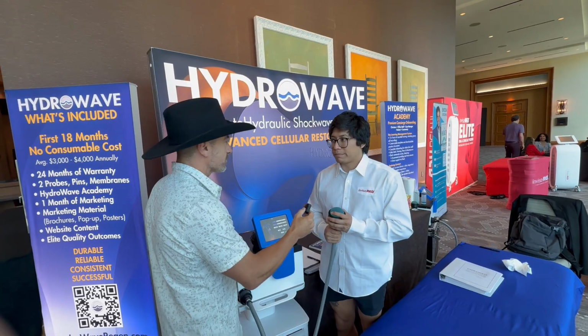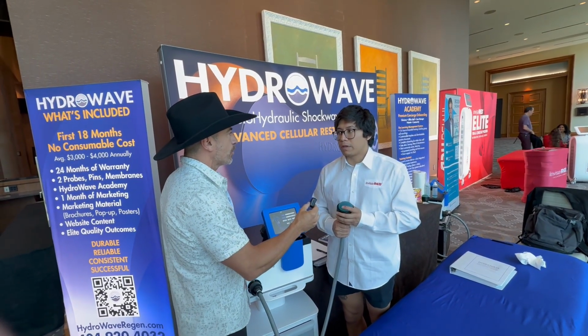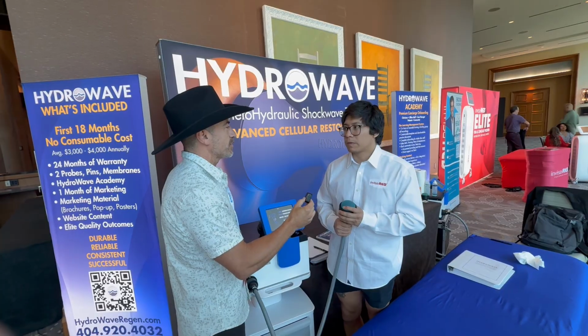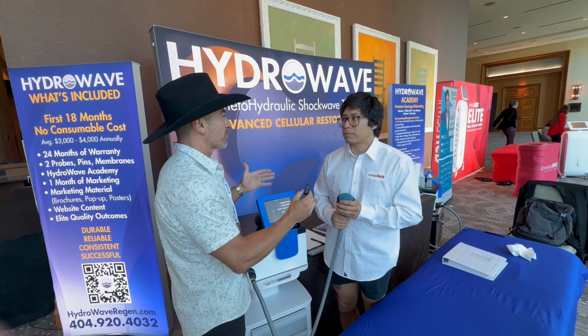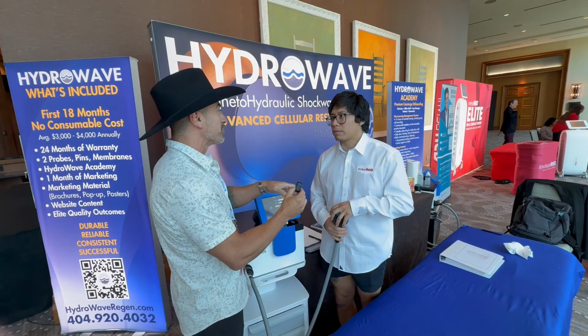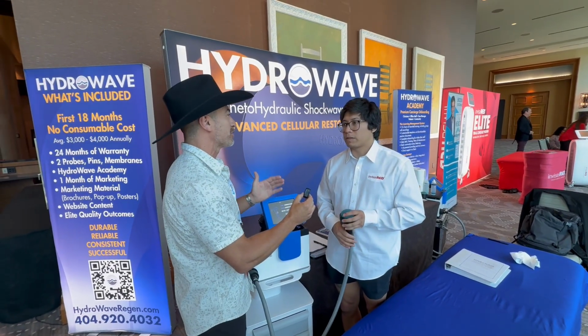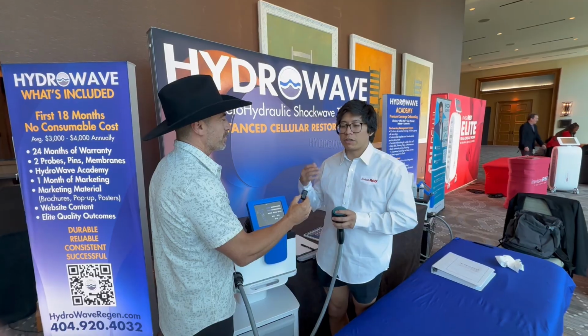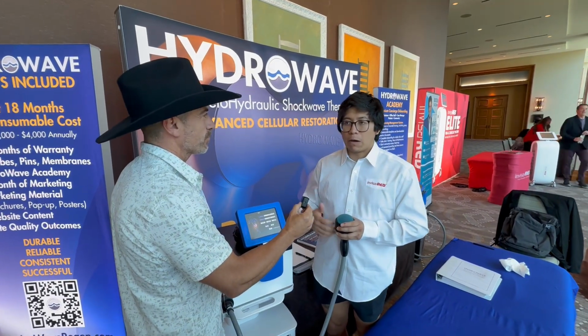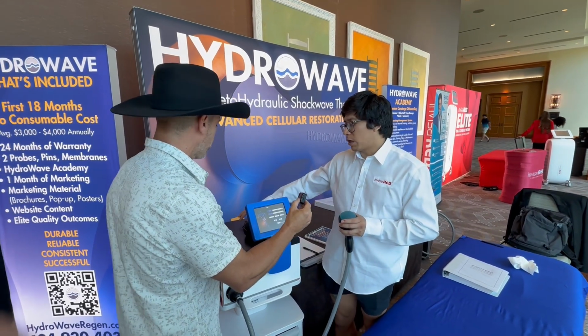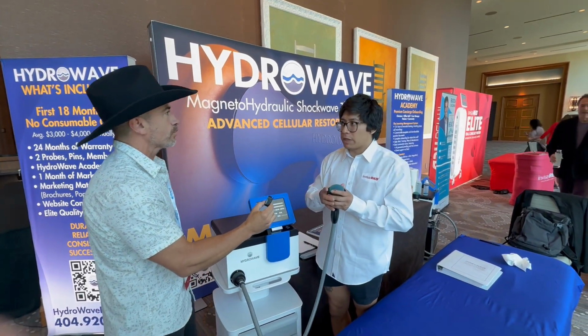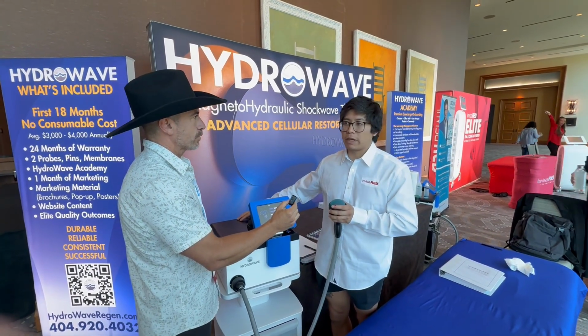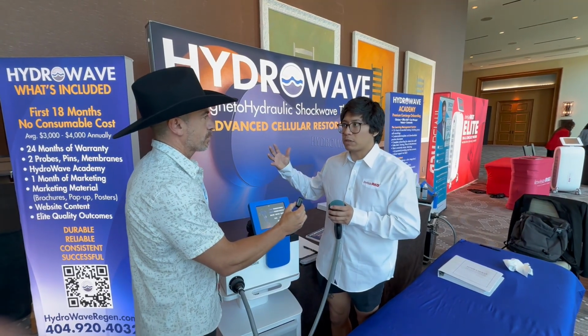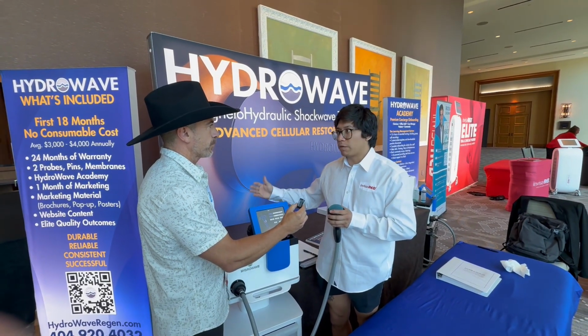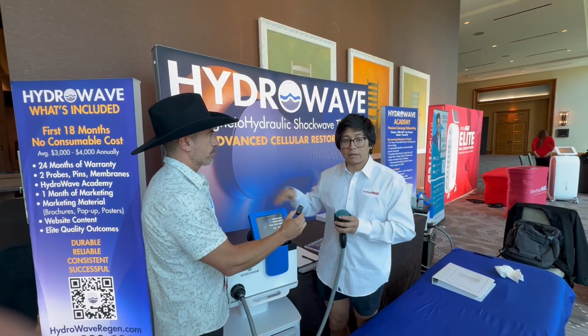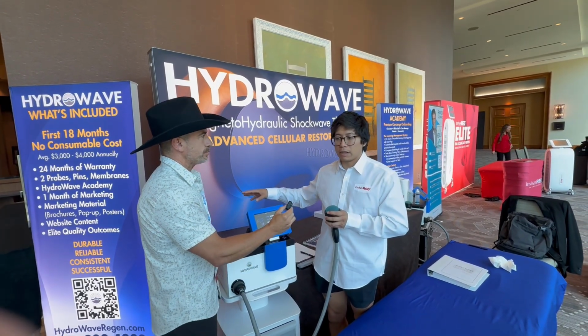One thing I've noticed is the sound is significantly different. Yes. Why is this quiet? Because I've been around other ones for so long, it seems like I'm not getting as much energy, like there's no way it can produce that much energy because it's so quiet. Yeah, so you want to associate loud sounds with a lot of energy, right? Ours is doing the same thing. It's just that we have that spark that all the heads have at the top of the head inside the machine with a dampener. That dampener quiets the spark noise that we hear, and keeps it away from the actual applicator. So it stays safe, it doesn't get corroded, and that itself will last long.